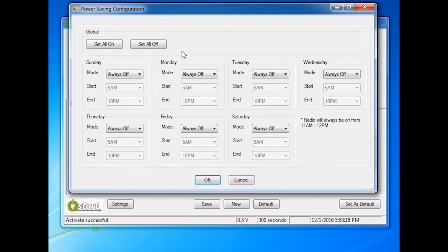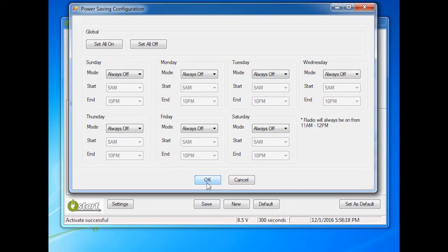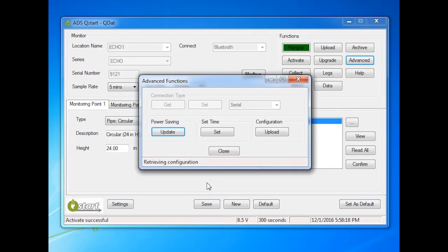The Echo is delivered with power to the modem set to Always Off. With this setting, the monitor automatically powers up the wireless modem each day between 11 a.m. to 12 p.m. to receive incoming calls. Note that the Echo will still deliver data and alarm notifications regardless of the Power Saving configuration. Refer to the Echo QStart Quick Reference Guide to make any changes. Changing from the factory setting of Always Off will impact your battery consumption. Click OK to save any changes to the Power Saving parameters.